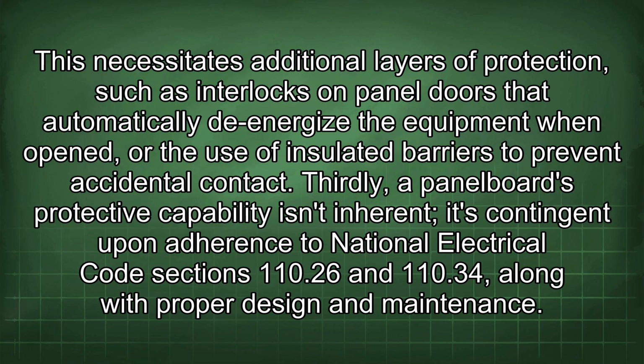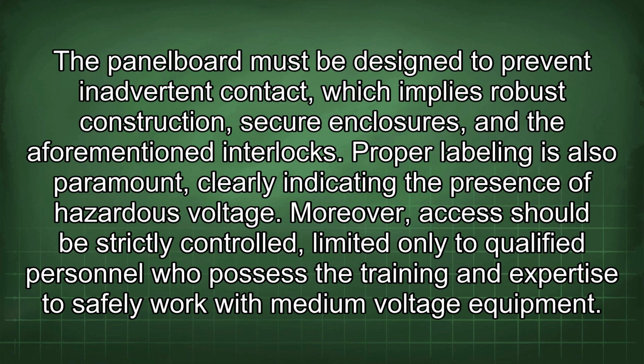Thirdly, a panelboard's protective capability isn't inherent. It's contingent upon adherence to National Electrical Code Sections 110.26 and 110.34, along with proper design and maintenance. The panelboard must be designed to prevent inadvertent contact, which implies robust construction, secure enclosures, and the aforementioned interlocks. Proper labeling is also paramount, clearly indicating the presence of hazardous voltage. Moreover, access should be strictly controlled, limited only to qualified personnel who possess the training and expertise to safely work with medium voltage equipment.